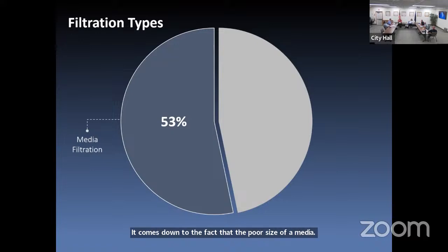You look at the diameter of the waterborne pathogens that you're trying to eliminate: Giardia, Cryptosporidium. Giardia cysts are 10 to 20 microns. Cryptosporidiums are like 4 to 6 microns. They're very small. So to give you a graphic on this, let's just assume these little black lines that I threw up there, you're looking at a cross-section of your filter media. Those white spaces in there are the pore sizes, the median pore size of your filter.